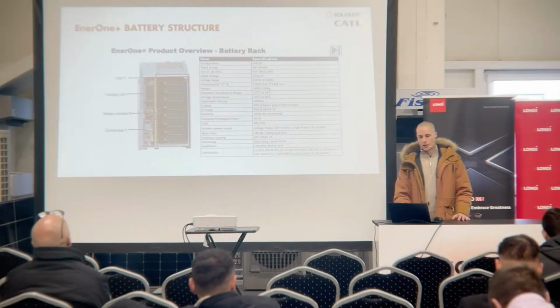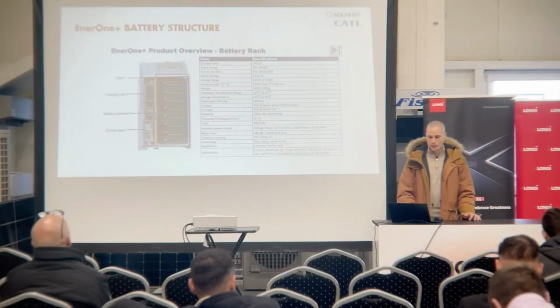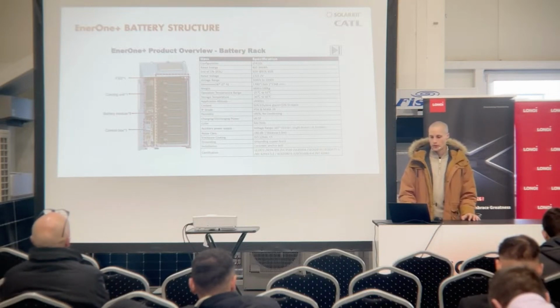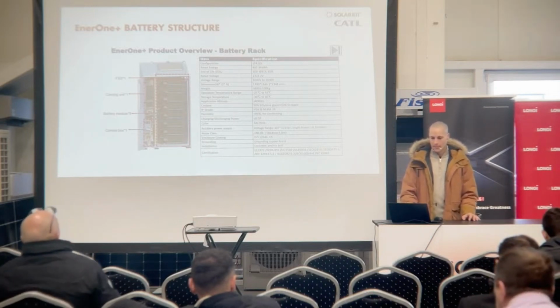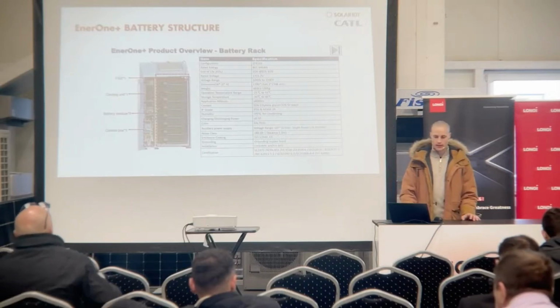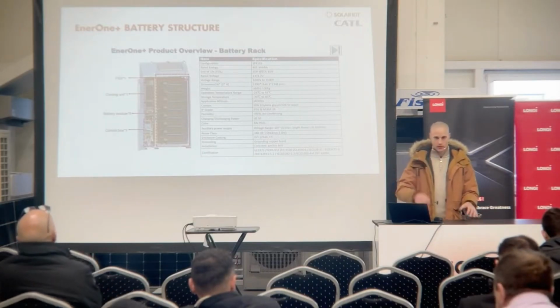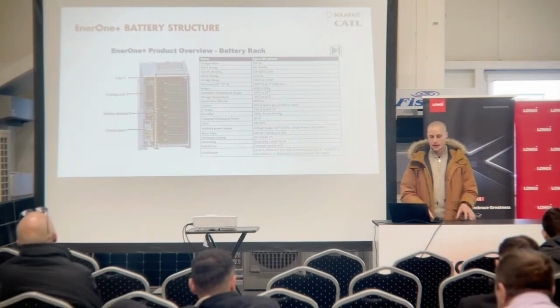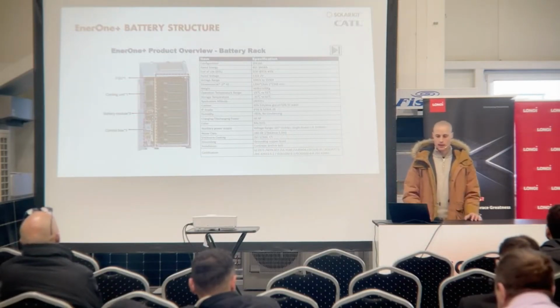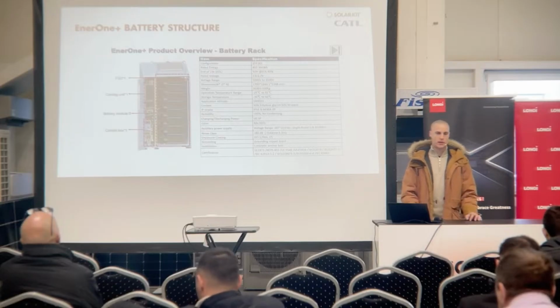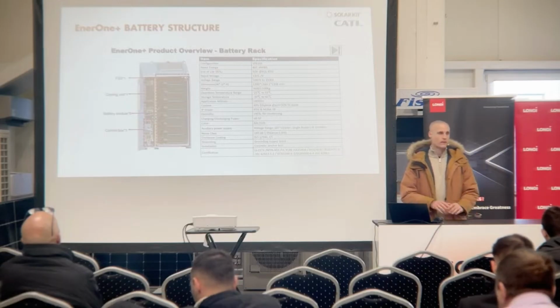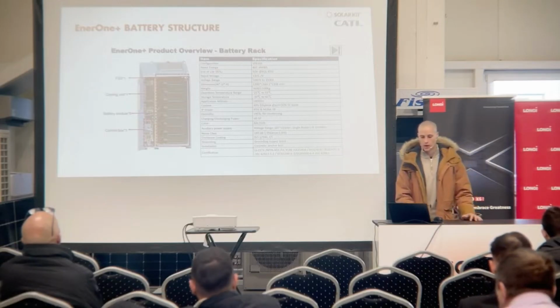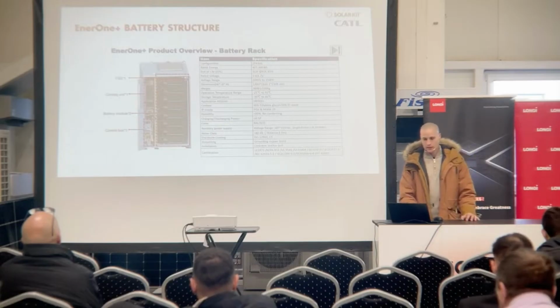So here's an overview of the cabinet solution. It's the 407 kilowatt hour EnerOne Plus. As you can see, it's all liquid cooling. It has everything inside, so no need to assemble anything on site inside the cabinet, because all the pipes, coolings, and connections are done. You just have to install one DC plus and one DC minus cable and connect it to the PCS, and it's ready to run.